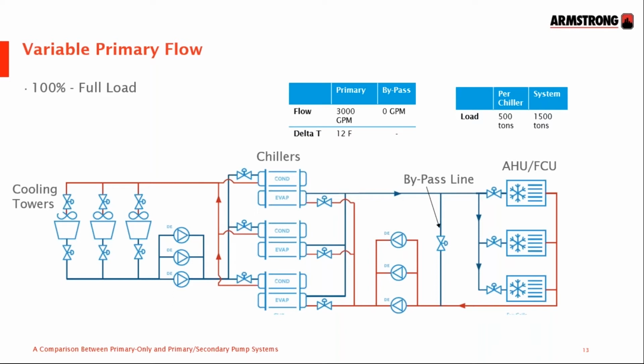The reason why is that there isn't a second set of pumps or pump valves, and you take their resistance out of the equation, resulting in a lower foot of head for the primary pumps, which will help reduce the power absorbed by this variable primary system.